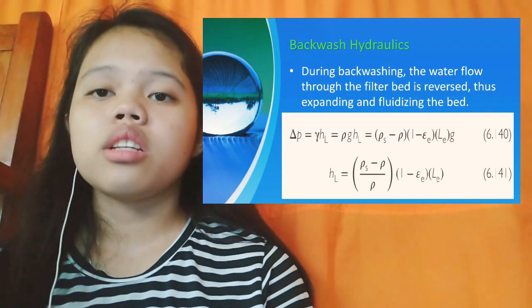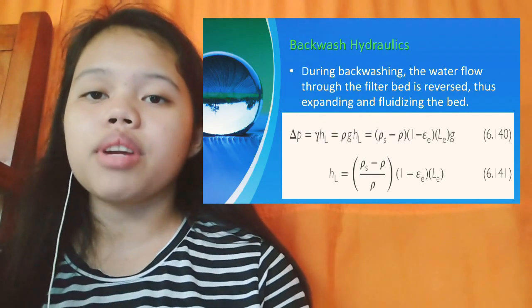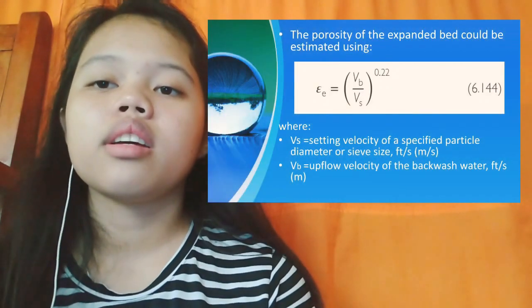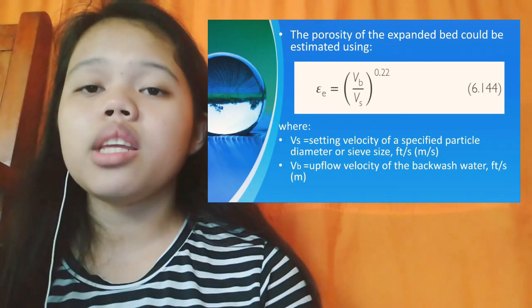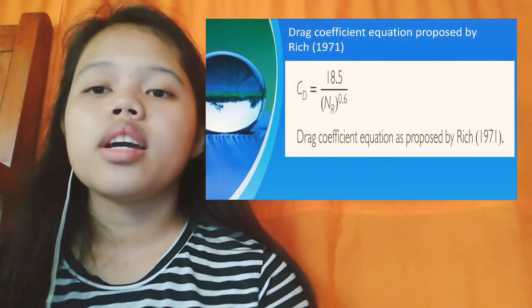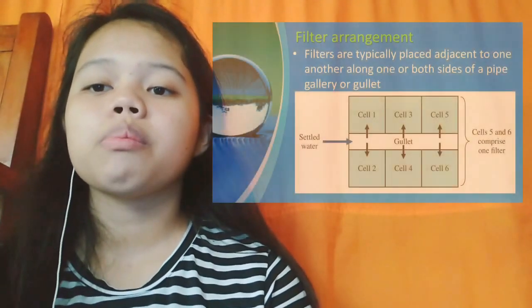Backwash hydraulics. During backwashing, the water flow through the filter bed is reversed, thus expanding and fluidizing the bed. The porosity of the expanded bed could be estimated using this equation. Drag coefficient equation proposed by Rich.